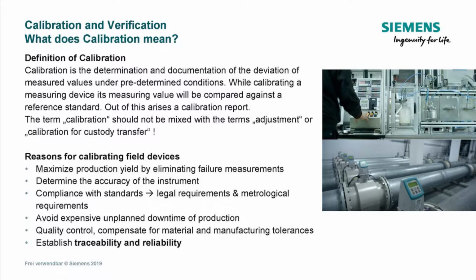Reasons for calibrating field devices. Maximize production yield by eliminating failure measurements. Determine the accuracy of the instrument. Compliance with standards for legal and metrological requirements. Avoid expensive unplanned downtime of production. Quality control, compensate for material and manufacturing tolerances. Establish traceability and reliability.